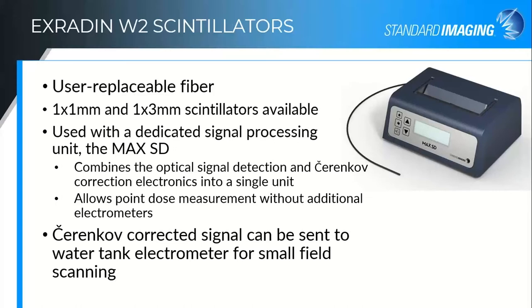The one by three also gives you three times the signal. So if you're scanning in slightly larger small fields where you may not need one millimeter length resolution on the scintillator, it gives you three times the signal-to-noise — a little bit nicer for some of the slightly larger fields.